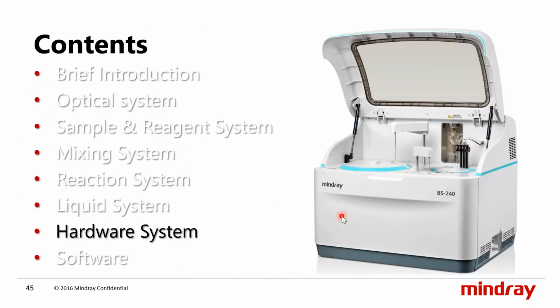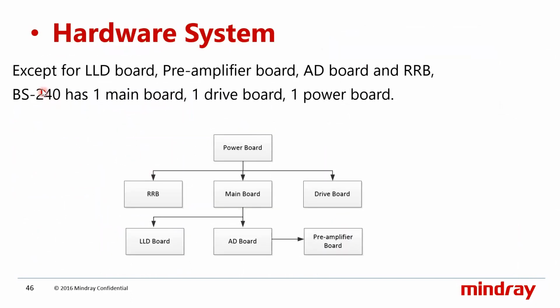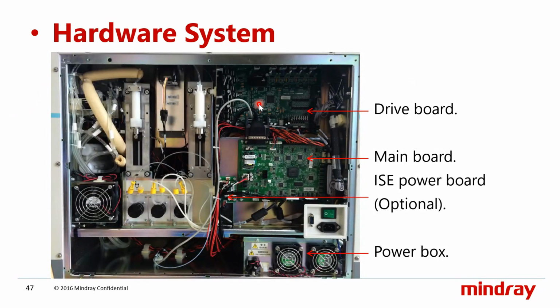So coming to the hardware system. Except for the LLD board, pre-amplifier board, AD board, and RRB, the BS-240 has one main board, one drive board, and one power board. If you open the instrument's back cover, you are able to see this drive board. This is the driver board, which is responsible for all the motors, pumps, valves, syringes, everything. And this is the main board.